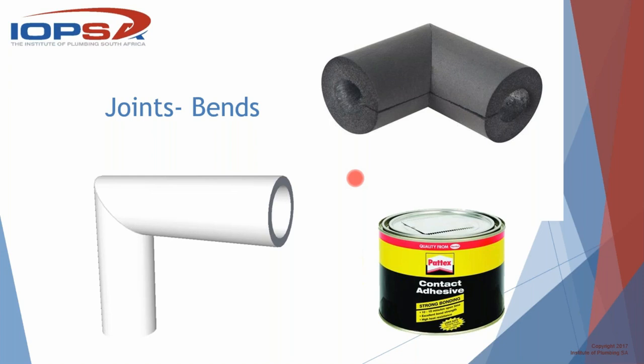When I had to cut for small pieces of pipe that's already in situ, usually you'd slip it on, hold it back, and then solder or do the joint and then allow it to fall back so that you don't have to cut the tube. But when there's very small pieces of pipe and you can't really do that, you've got to almost solder first and then cut a piece down the middle on one side, slip it over, and then glue that slit back together again. That didn't happen very often because it only had to be done on small pieces of pipe.